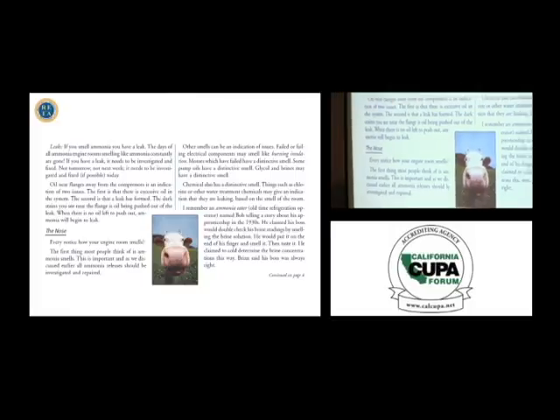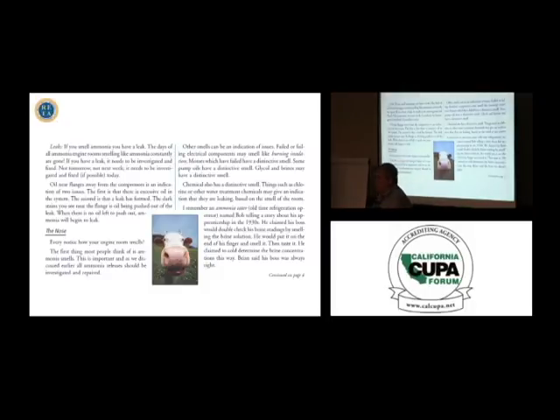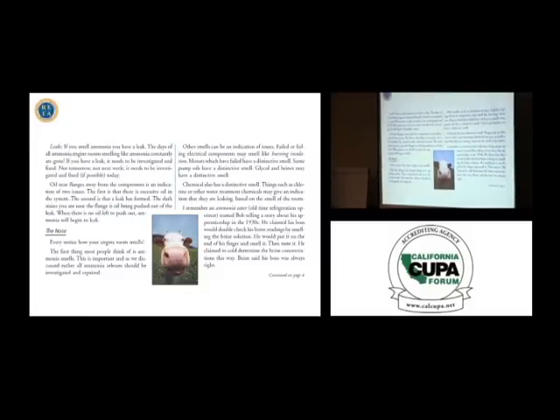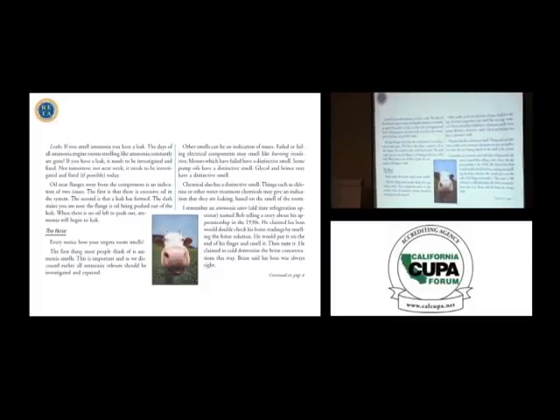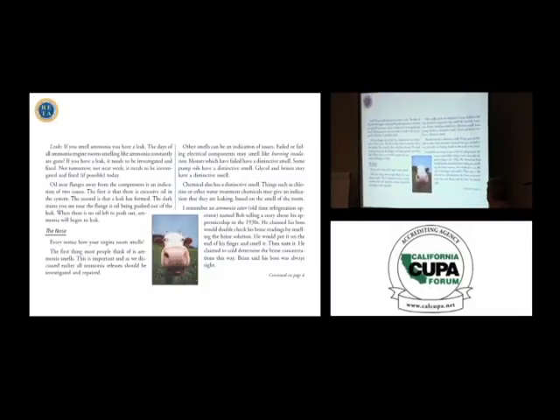Next. So then, what's the next tool you have? You've got your nose. Now, I will give you a personal monitor, 0 to 400, and the reason for it is not that you're going to know that you have the ammonia before your nose does. Your nose will do that for you, but it'll tell you how bad it is. Sometimes we have to work in an environment where it is kind of stinky, and we want to make sure that if we're wearing our air purifying respirators and our level D coveralls to deal with a seal leak or packing on a valve, that we are working in an environment that our respirator is rated for. That's one of the purposes of that personal monitor. That's something I'll give you. I don't read in code that I have to supply that to everybody, but it's my elective to provide that. The nose, though, is a great example.